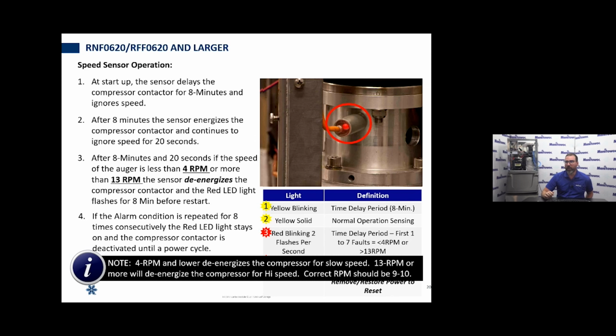Now you could figure that out by counting. You can take that sensor out and you can actually see inside and look at that coupling. There'll be notches in it. You can count the times that you see that notch. There's 2 notches per revolution, so keep that in mind. But that'd be the easiest way to verify that you do have operation. You'll probably be able to tell if it's turning or not just by the sound of it. All these machines tend to make a little bit of noise, and you start to pick that up after you've been around them long enough. But if you're unsure, you can always unscrew that sensor and look directly in there.